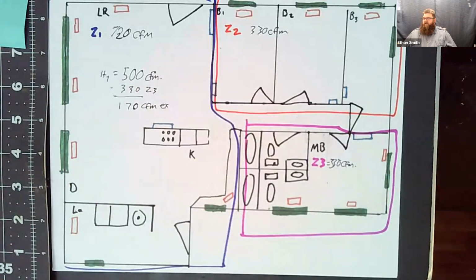Okay. So I've got 170 CFM. So we can run a bypass. It's a gas furnace, so we can't really turn the blower down too much. Can a little bit, but not a whole lot. So we want to put this somewhere where it's going to, A, not cost us any more to run. So the bypass is out. And we also want to manage that excess air so we don't put excessive wear and tear on our equipment. Because even if we didn't do anything with that 170 CFM, the system would run hot, which would cause extra wear and tear on my furnace. So we want to eliminate that as well.